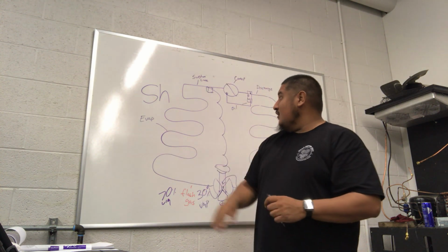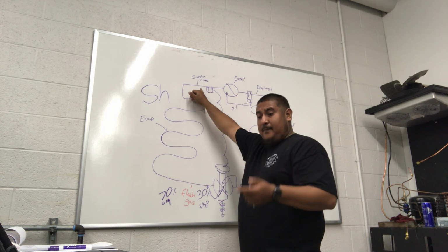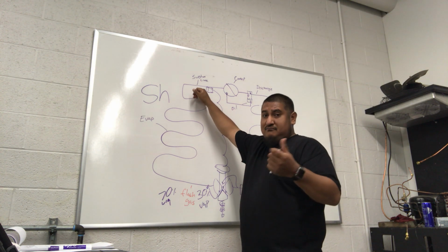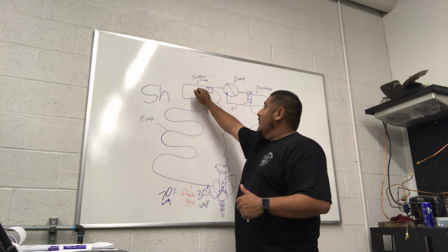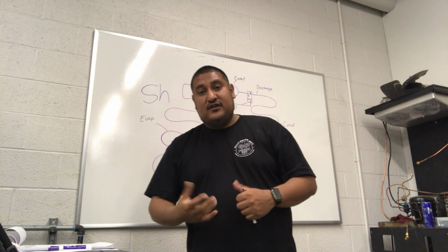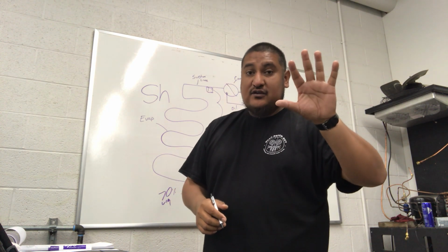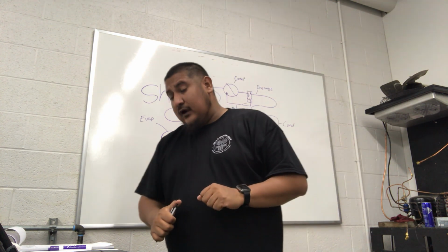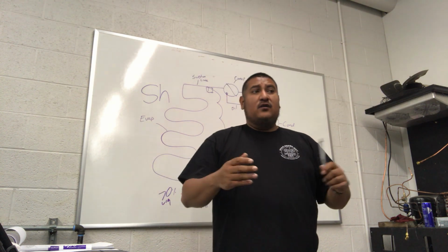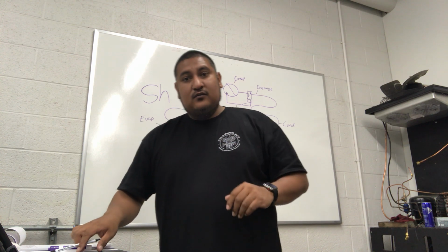When we look at our suction pressure, the converted temperature is 40 degrees. But when we check our suction line temperature, it tells us we're at 45 degrees. So that means we picked up 5 degrees of superheat. Normally you want to be above 10 degrees of superheat. That's kind of the rule of thumb.